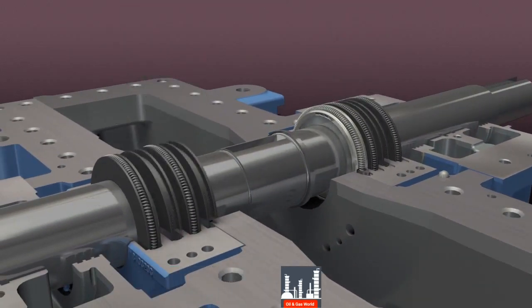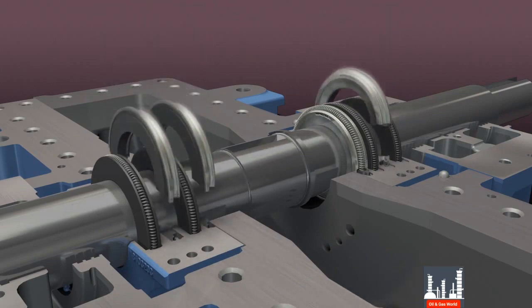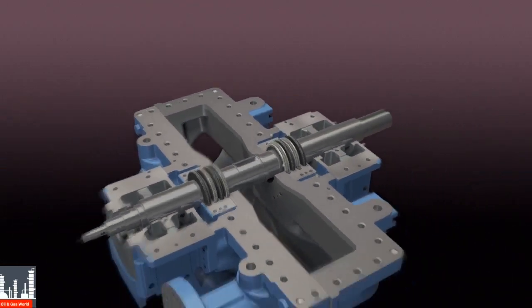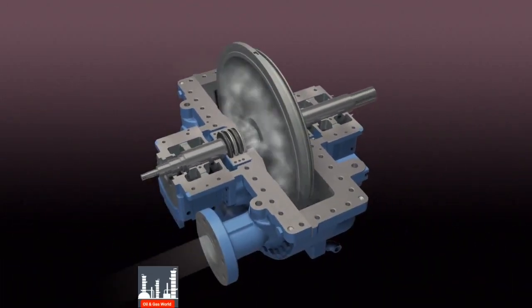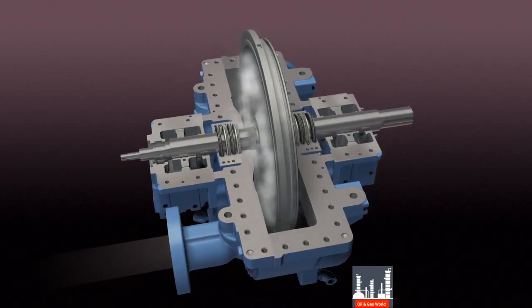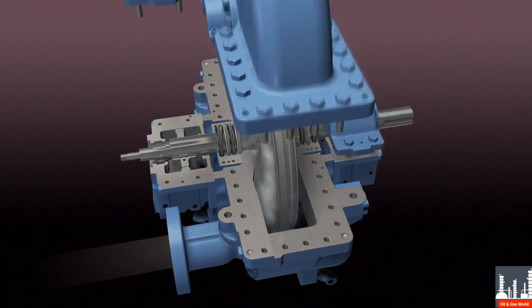Typically, two Sentinel floating brush seals are installed in each gland box to provide superior sealing, while protecting downstream carbon rings from contamination and high pressure, improving overall performance.